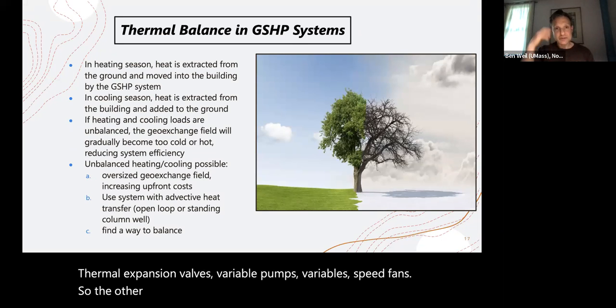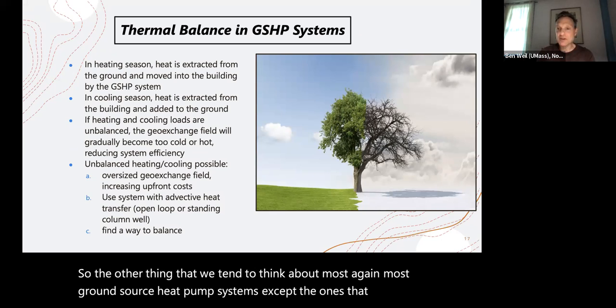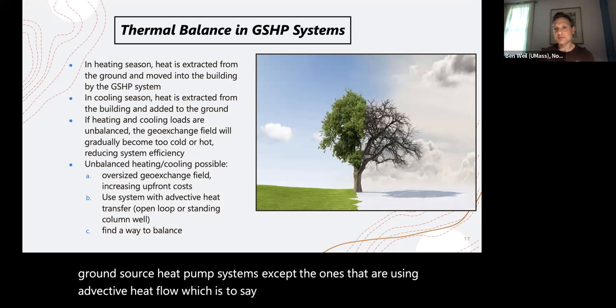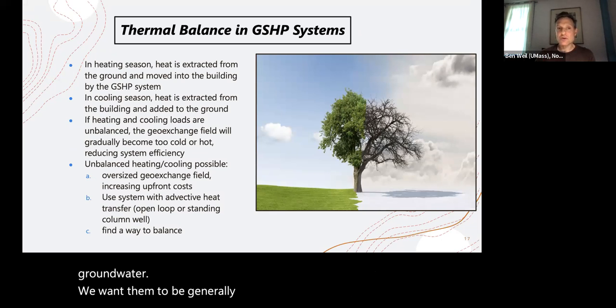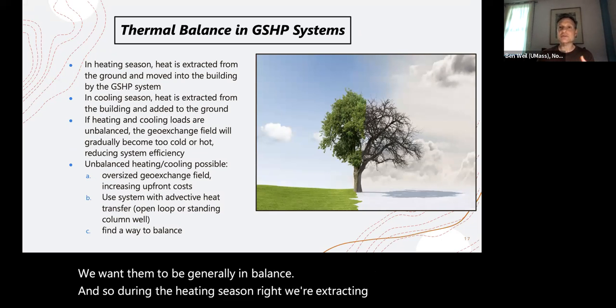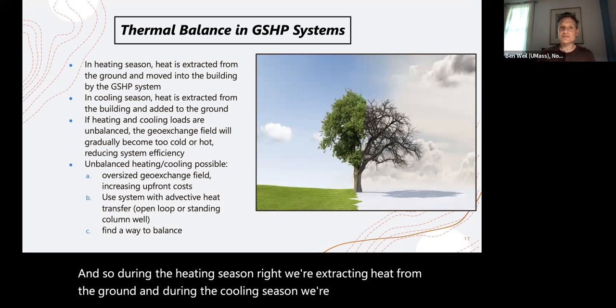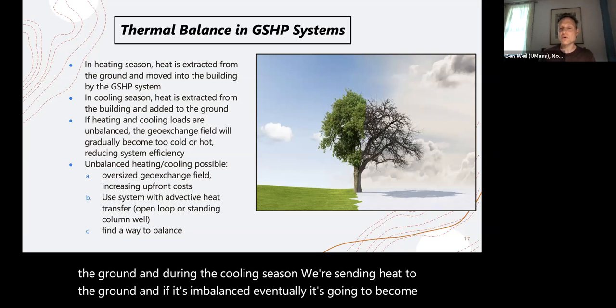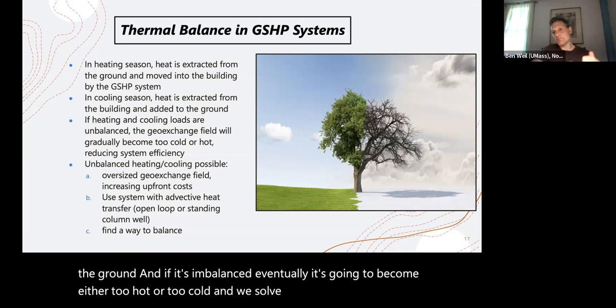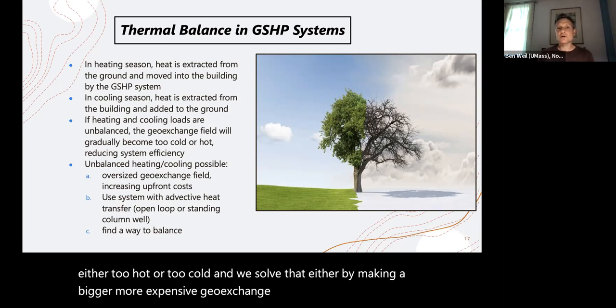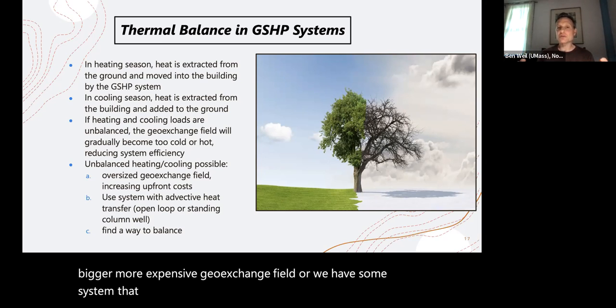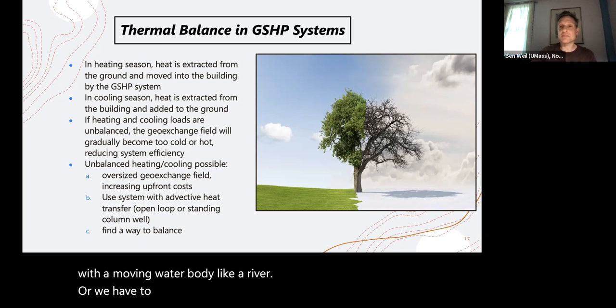The other thing that we tend to think about, with most ground source heat pump systems, except the ones that are using advective heat flow, which is to say we're bringing in new groundwater, is that we want them to be generally in balance. During the heating season we're extracting heat from the ground, and during the cooling season we're sending heat to the ground. And if it's imbalanced, eventually it's going to become either too hot or too cold. And we solve that either by making a bigger, more expensive geoexchange field, or we have some system like an open loop or standing column well, where we can move water in from elsewhere, or direct exchange with a moving water body like a river, or we have to find a way to make it balanced.